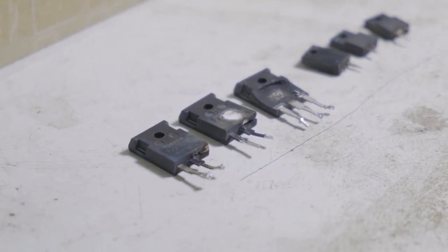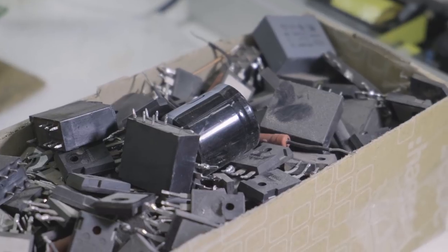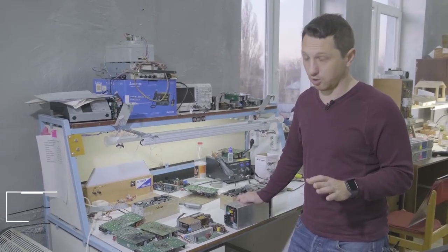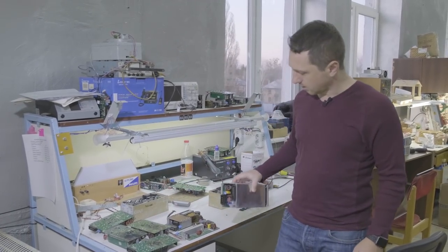The control module was only the tip of the iceberg. Most problems were found in the power modules. Stations broke down while in use, and sometimes literally burned down. Various elements burned up completely spontaneously. They were replaced, the modules were returned to the station, but after a while they burned again. There were so many different parts, and they just randomly burned down.